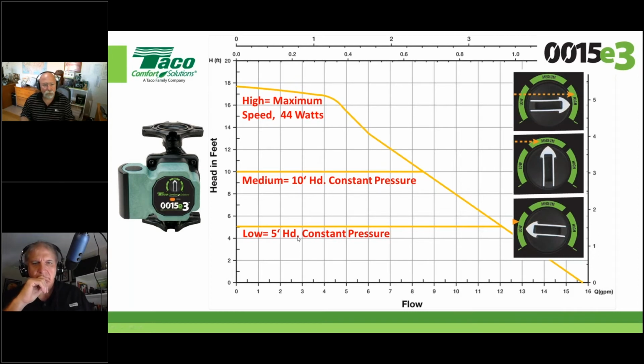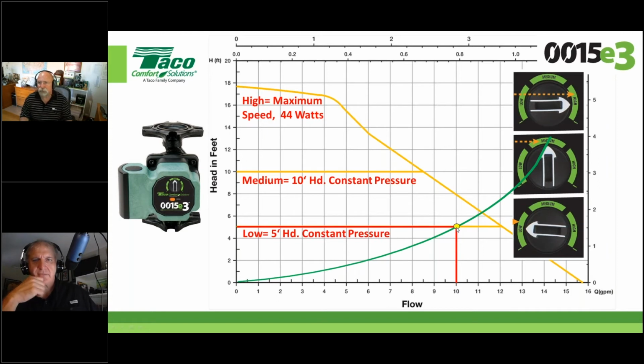Now, you're saying, well, didn't you tell me that I don't use automatic modes here? Don't worry about it. The automatic means it has to have an input. And in a boiler primary circulator configuration, you're never going to get hydraulic changes that the circulator needs to make a decision to speed up or slow down. So simply put, it's just going to come up here to 5 foot of head. We're right on 5 foot of head. This will be your operating point for that.